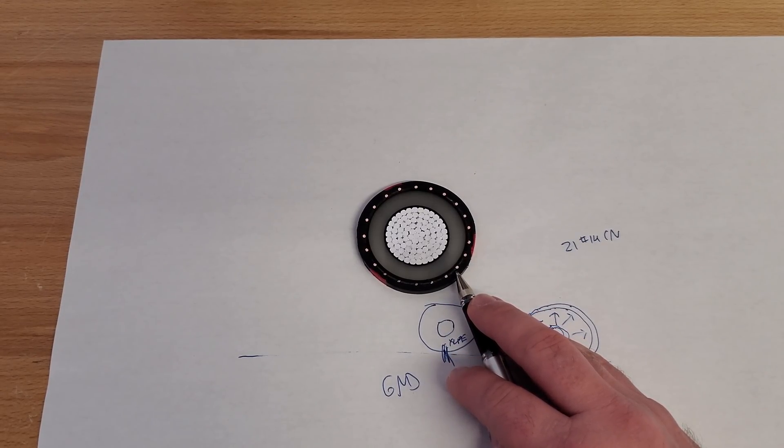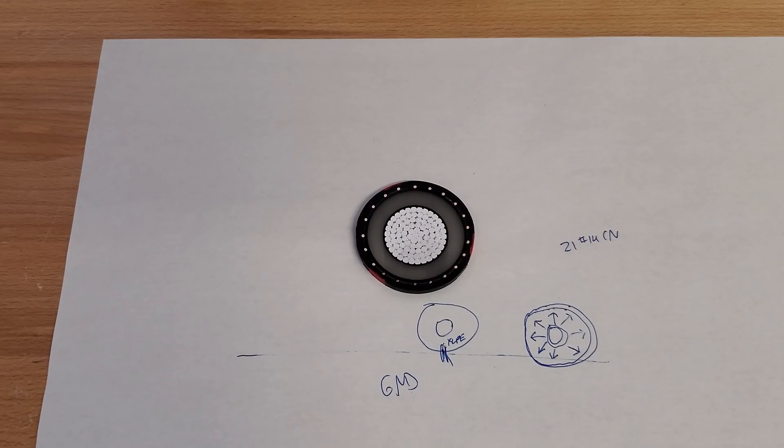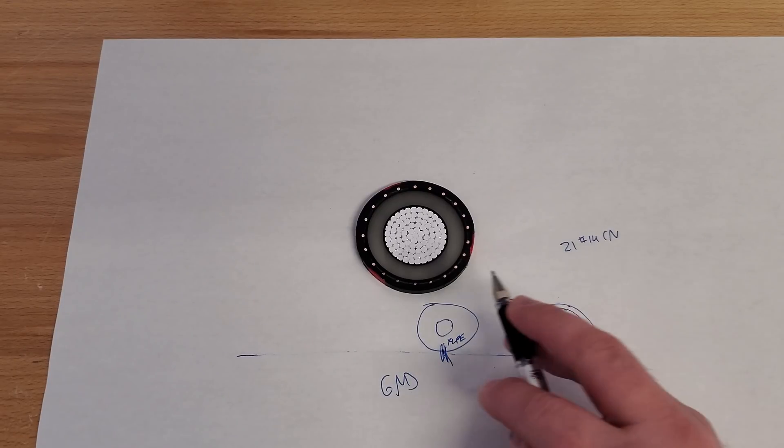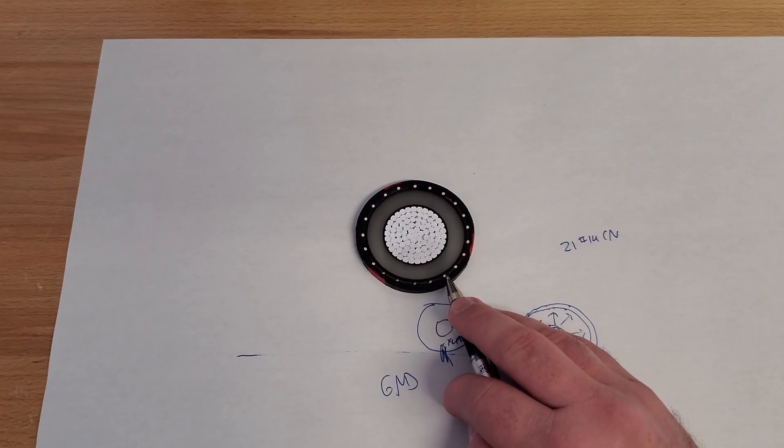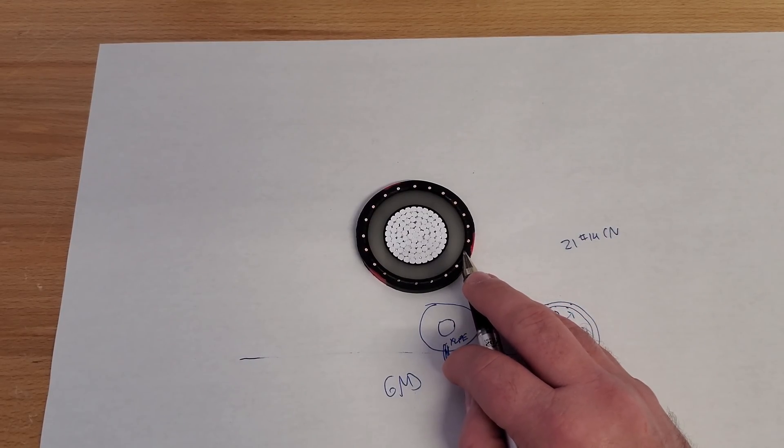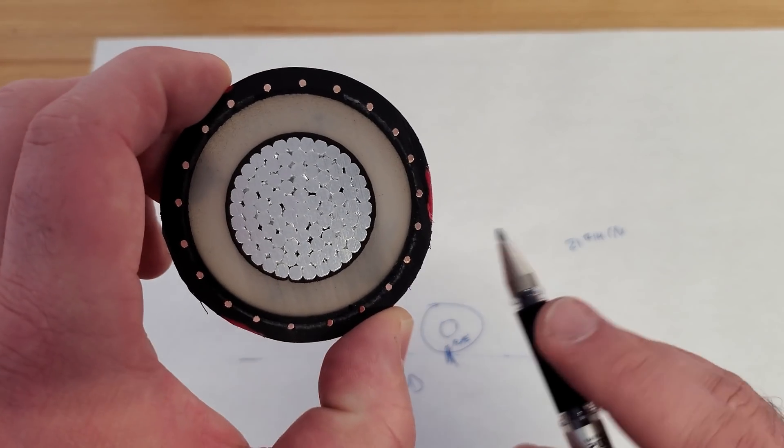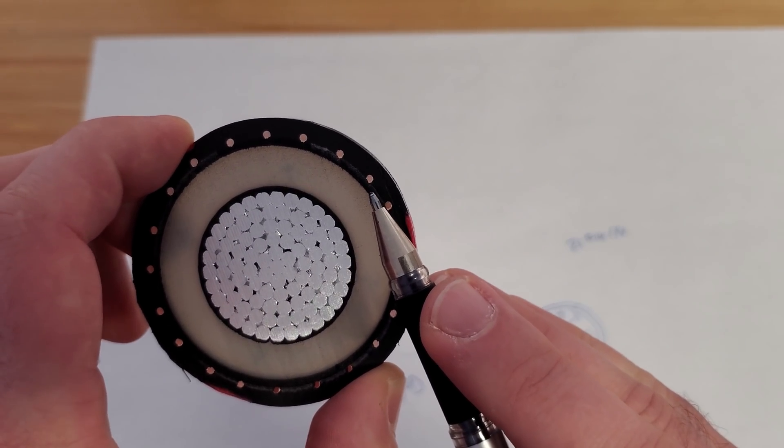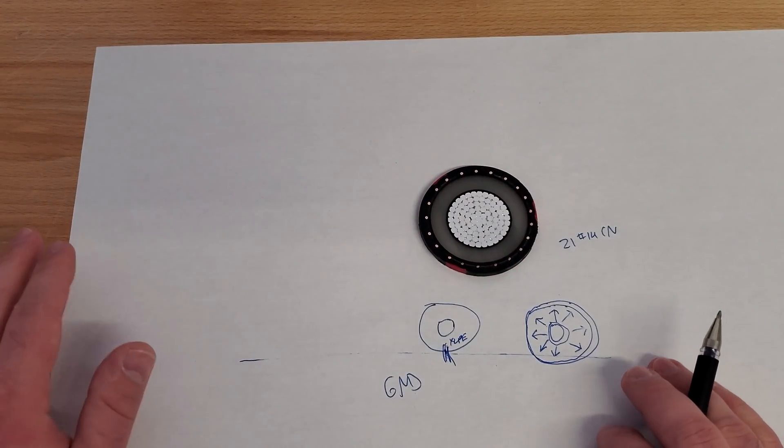It's also resistant to a wider amount of chemicals. Not that you're going to be spilling crazy chemicals on your cable, but it's just better having a slightly better and more resistant layer. So again, that's the LLDPE. We've installed cable without a jacket at all. And that's perfectly fine. Functionally what you'll see on the outside are the concentric neutral layers. Nothing wrong with that at all. It's just not wise in my opinion, because if you have a rock or anything like that, that may scrape or puncture through this semi-con layer, you're done. It's going to blow up and you have to replace it.